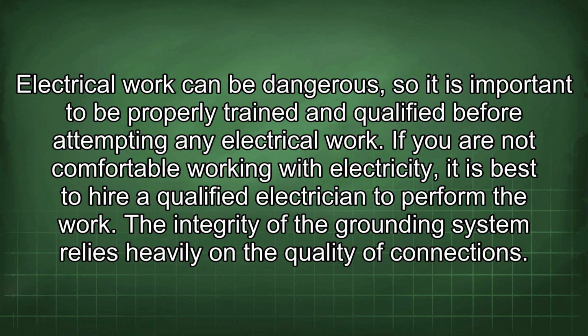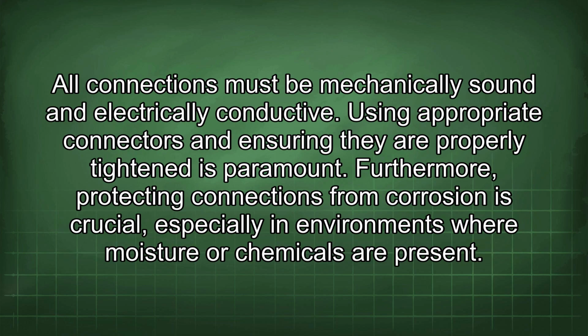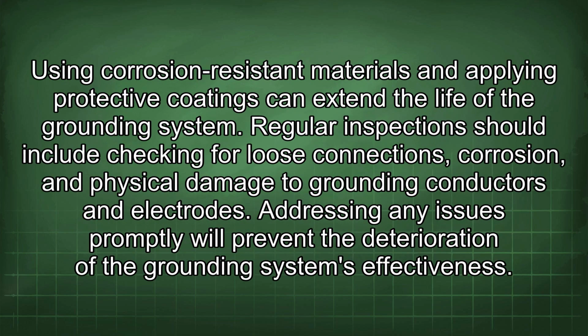The integrity of the grounding system relies heavily on the quality of connections. All connections must be mechanically sound and electrically conductive. Using appropriate connectors and ensuring they are properly tightened is paramount. Furthermore, protecting connections from corrosion is crucial, especially in environments where moisture or chemicals are present. Using corrosion-resistant materials and applying protective coatings can extend the life of the grounding system.